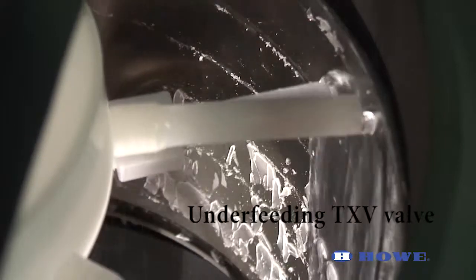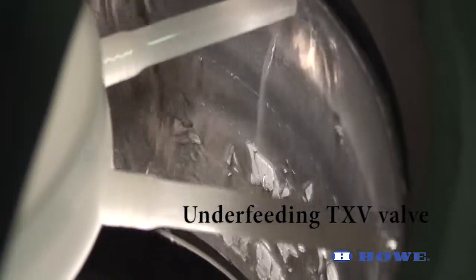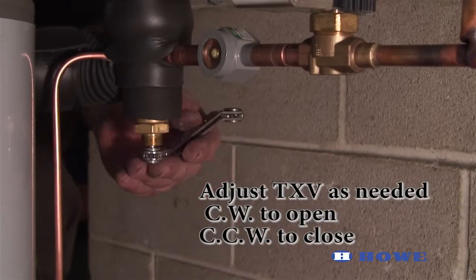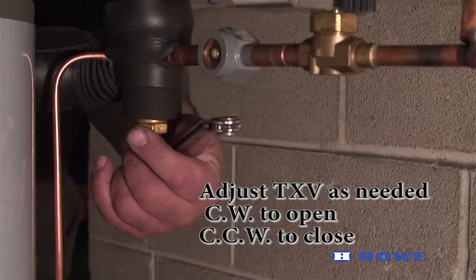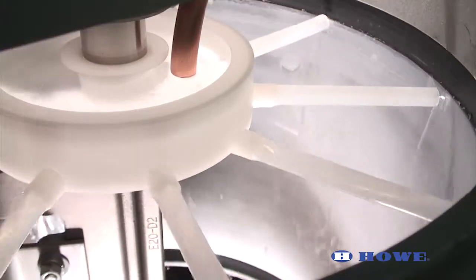If ice near the bottom is freezing but not harvesting, then the expansion valve is underfeeding and must be opened to allow more refrigerant into the evaporator. Open an underfeeding expansion valve by turning the valve adjustment stem out one quarter turn at a time. Wait between each adjustment to allow the TXV to balance out.